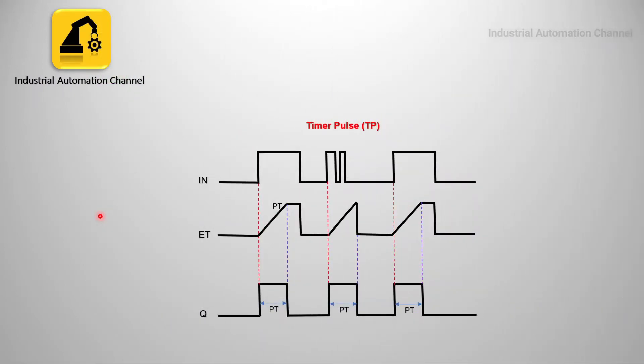Here we can see the function diagram of the pulse timer. This function is sensitive to the rising edge of the signal. If I press start, the output turns on and elapsed time starts counting. As soon as elapsed time reaches the preset time, the output turns off. Whenever I turn off start again, the elapsed time resets to 0. Even if the input is turned on and off during timing, the elapsed time continues to count, and the repeated input changes have no effect.